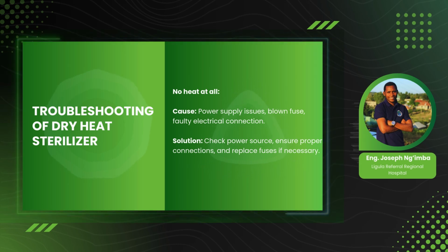The solution is to check the power source from the socket. This is important, because for those of us who work in hospitals, they call you and say that the machine does not light up. But if you check the socket, the socket is off. So it is important to check from the socket that the power is flowing. If the socket is off, you'll have to turn it on. You'll have to ensure proper connection. And if you inspect and realize that there's a blown switch or blown fuse, you'll have to replace it.